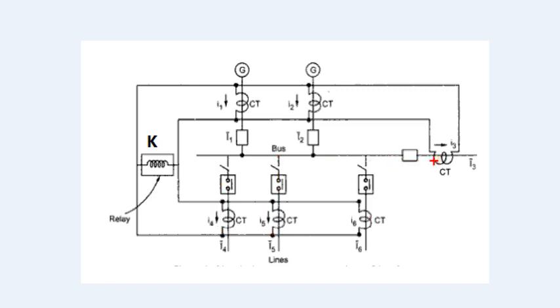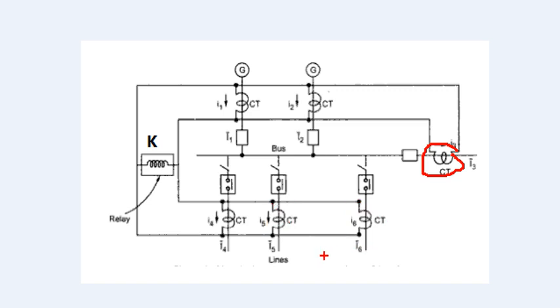We place CTs on each connection — one CT on each incoming and outgoing side. We connect them together at a common junction for differential protection.